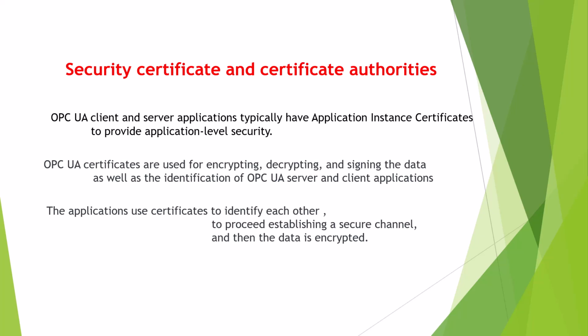Security certification and the certificate authority. This is very important in OPC UA. The OPC UA client and the server application have application instance certificates to provide application-level security. So you have to confirm the security certification or certificate authority. If you're not confirmed, you can't do OPC UA.